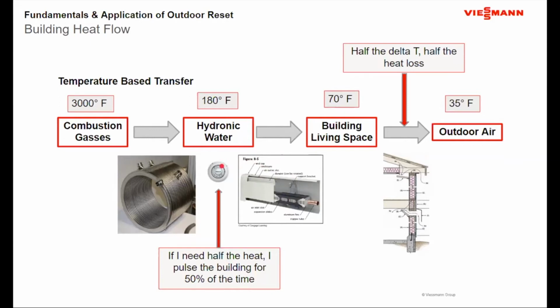So if I need half the heat, basically the thermostat controls either a control valve or a zone pump to apply flow to my heat emitter for about half the time period. So it might be 3 minutes on and 3 minutes off, 4 minutes on, 4 minutes off. But the end result is, after that 1 hour period, if I look at my control valve open time versus closed, or my pump on time versus off, it's 50% on either side. Okay, so this stays constant, this stays constant. This will vary a little bit because of the thermostat, but the end result is I'll get a pretty decent balance between the two of these.